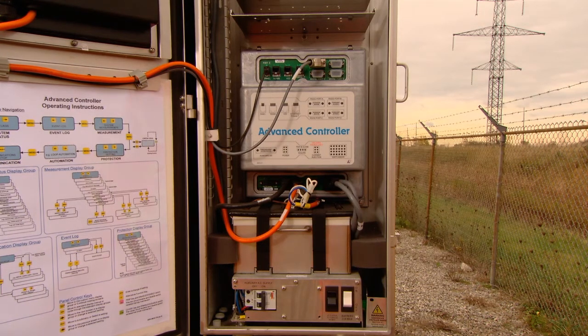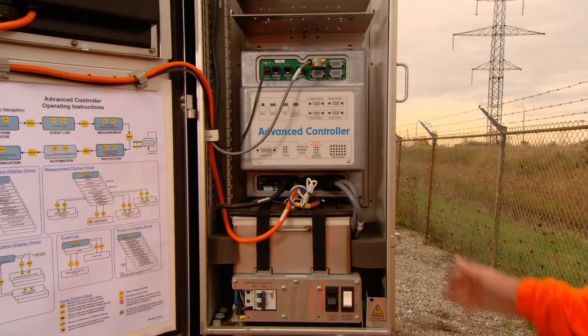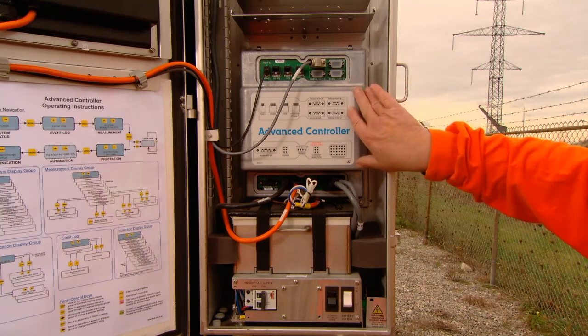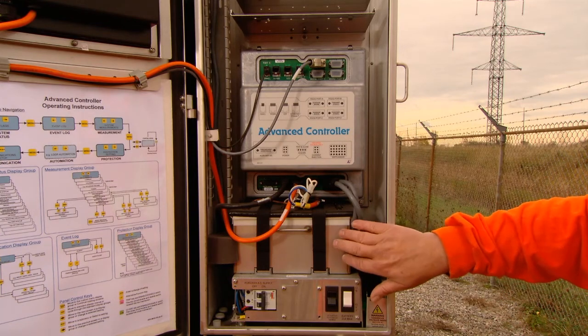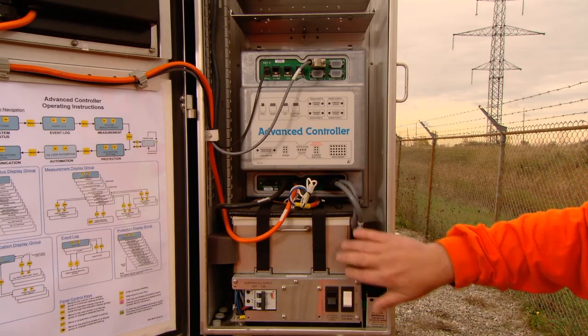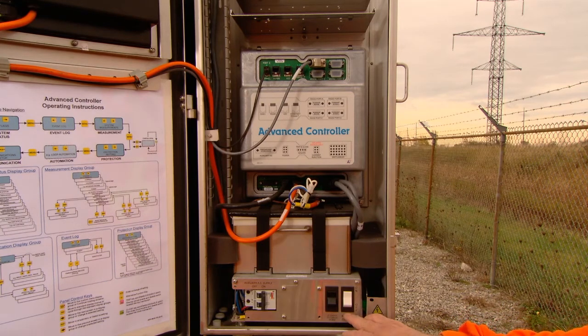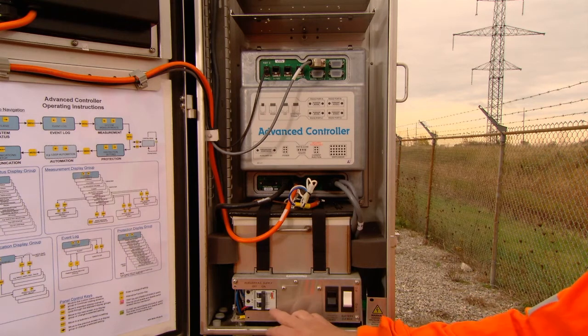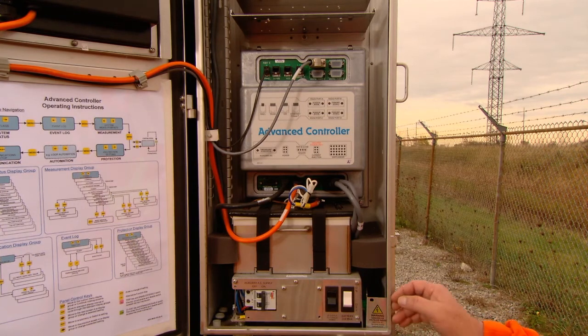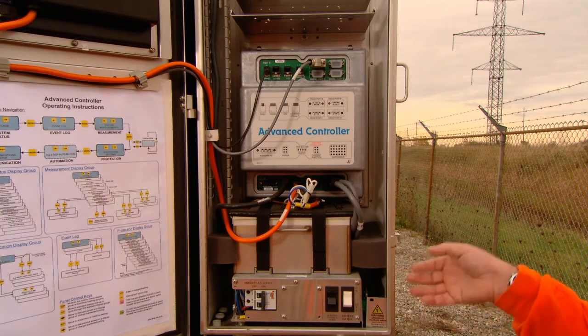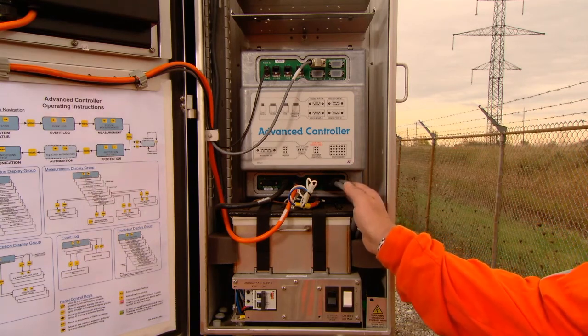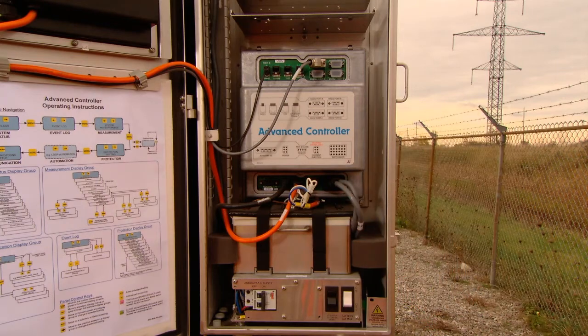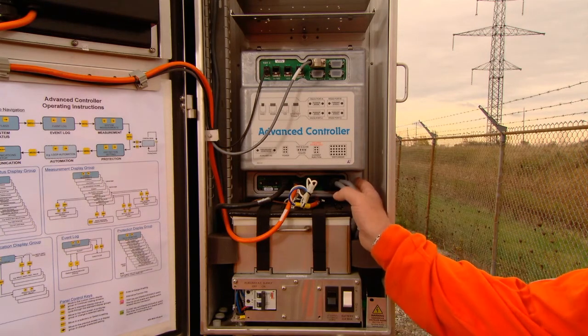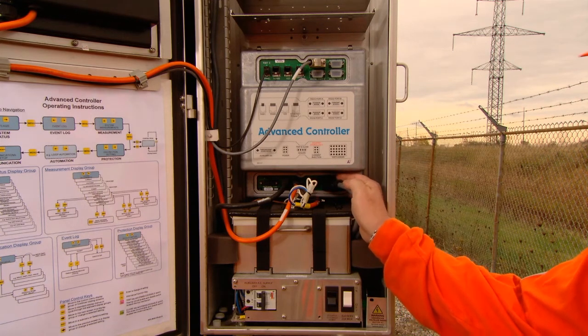Upon opening the main door, you will find the main processor. It has the words Advanced Controller on its cover. Below the main processor, you will find the batteries. Resting beneath the batteries are 3 breakers, one for the battery, one for the voltage supply, and the main containment breaker for the entire unit. Also housed within the unit is an outlet for the gray-colored communication cables, which connect to the recloser. These are plugged directly into the main processor.